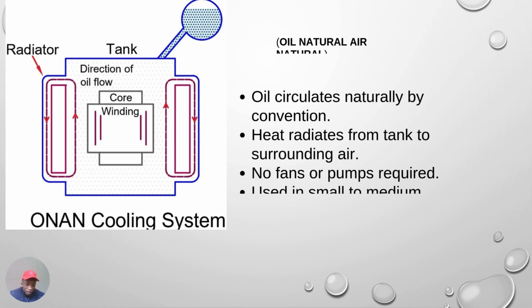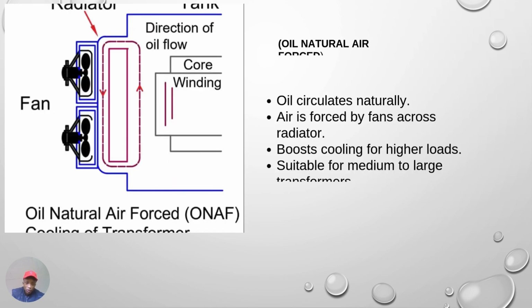Now let's see if you understood. We have said there are four transformer cooling methods: ONAN, which is oil natural, air natural; ONAF, which is oil natural, air forced; OFWF, which is oil forced, water forced; and OFAF, which is oil forced, air forced. Looking at the diagram of the ONAF, you can see the fans over there, but the oil is natural.